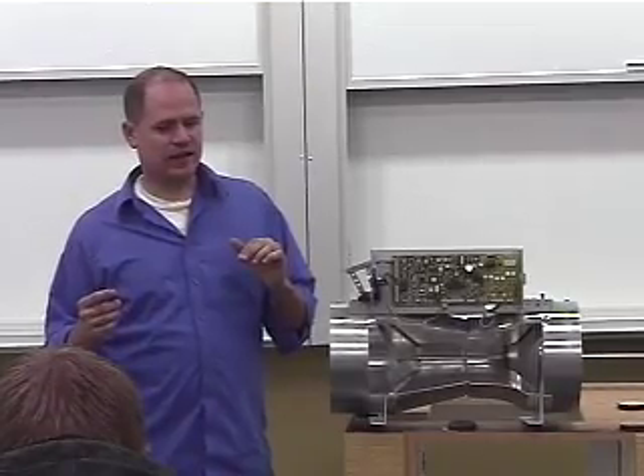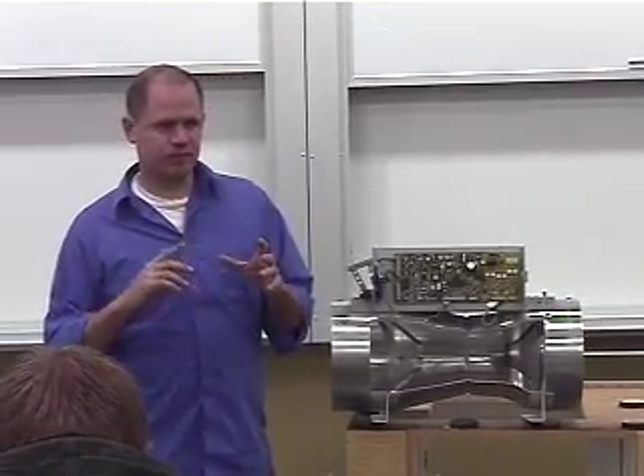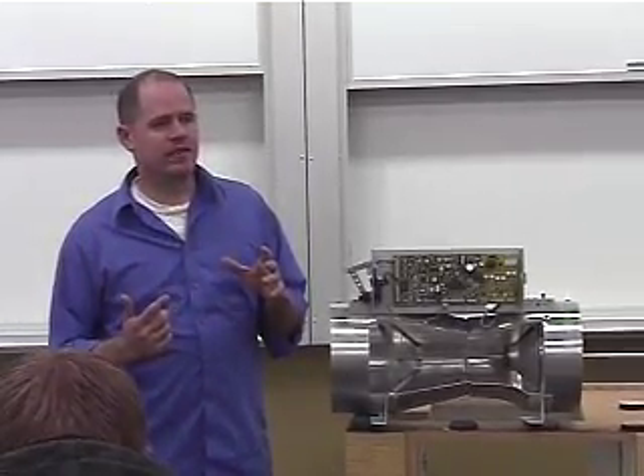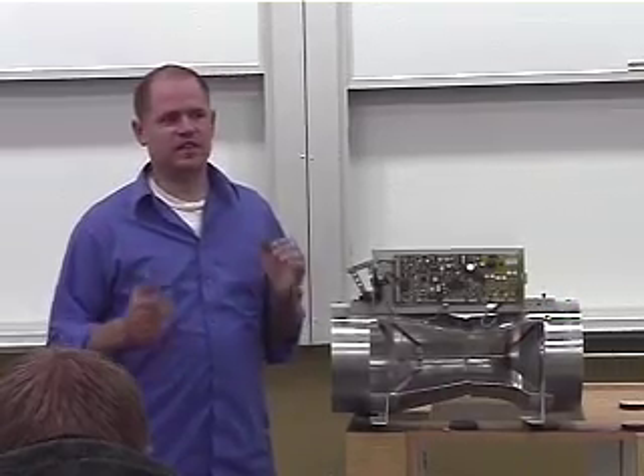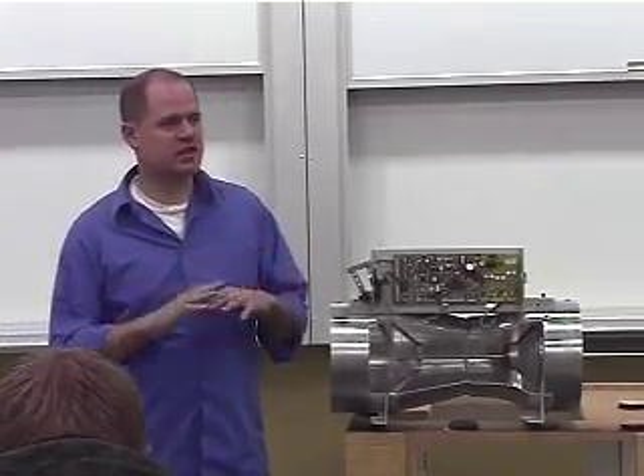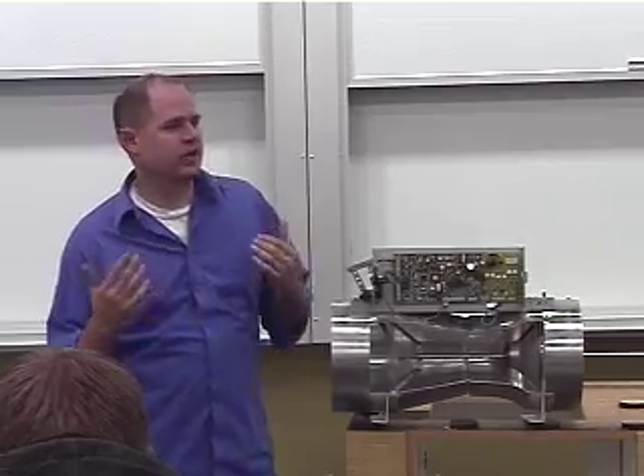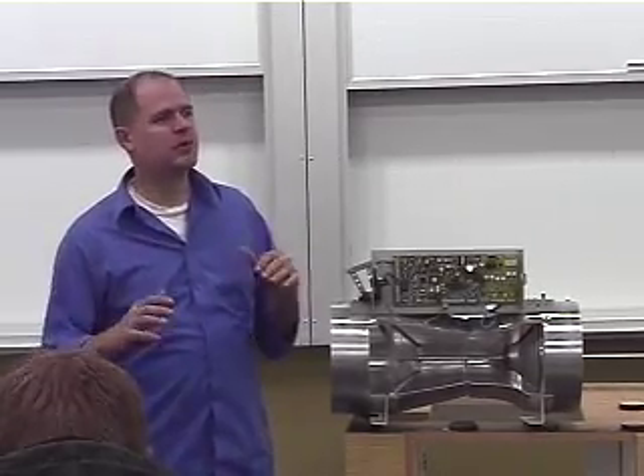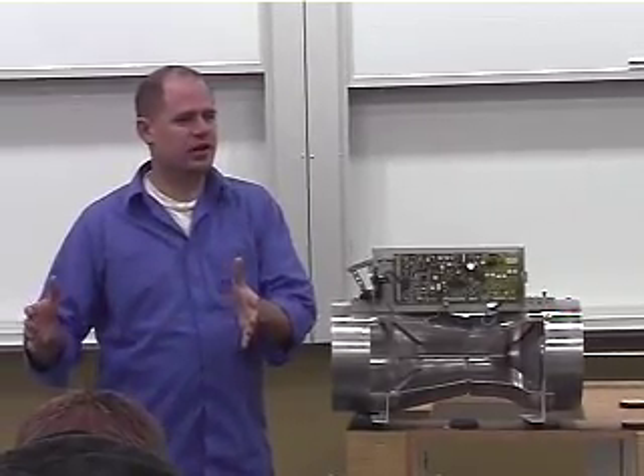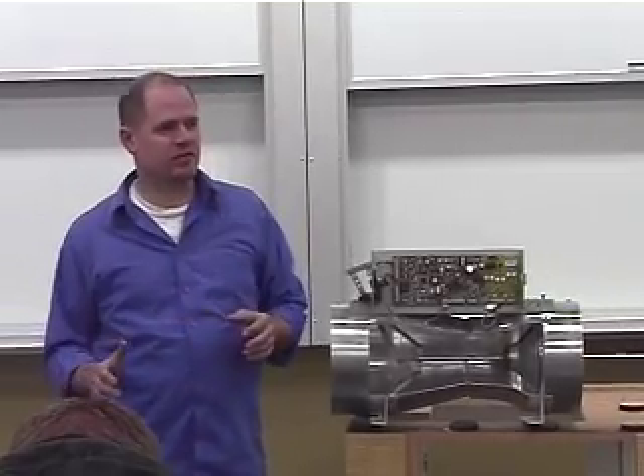The only one that I've seen in a fume hood lab that is not typically high-speed is a snorkel. A lot of times those are constant volume, so they don't need to be high speed in any way. They'll put a low speed one on there and say, okay, just be in this position. The other stuff responds quickly to take care of the flows.